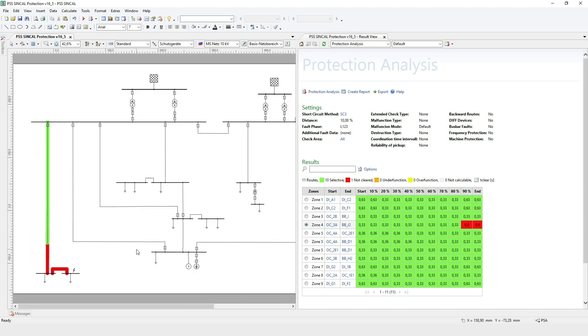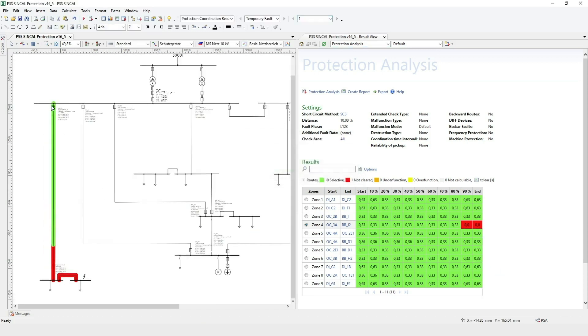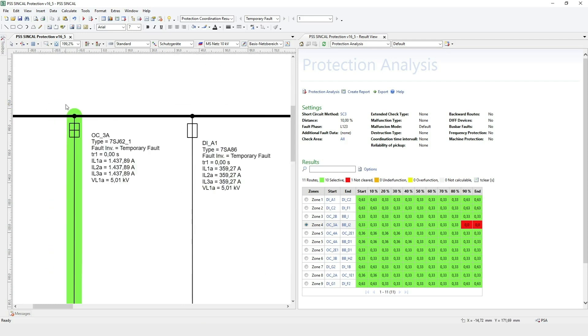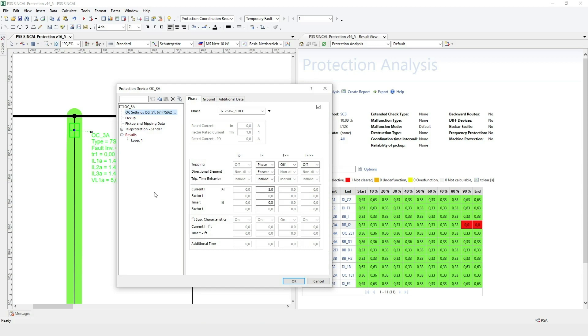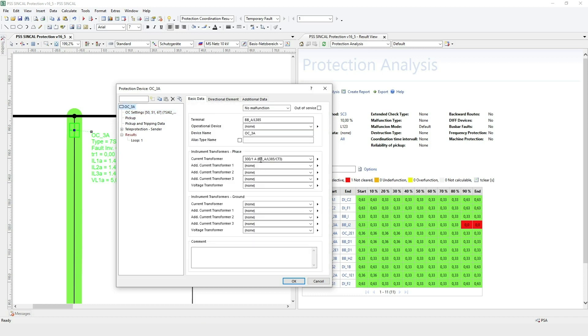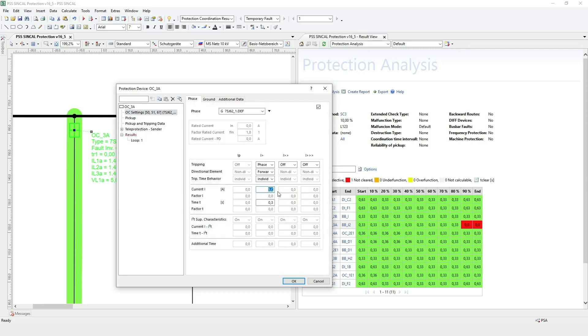Next, we'll investigate the not cleared fault locations. Performing the protection simulation, we see the main protection device could not clear the fault at the red fault locations — the device did not start. In this case, we have an over-current protection device. In the settings, we notice the tripping current is set to 5 amperes secondary, respectively 5 multiplied with the current transformer ratio 300/1 to 1.5 kiloamps primary. This is above the occurring short circuit current of 1437 amperes, so we must change the pickup current to make the device more sensitive.